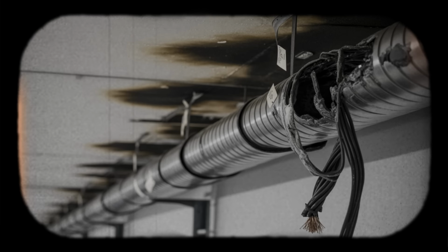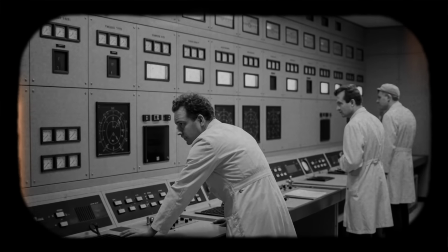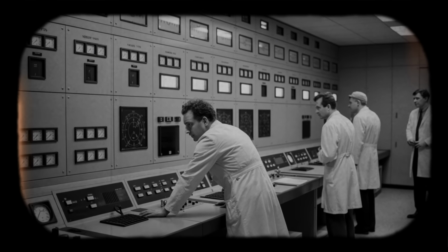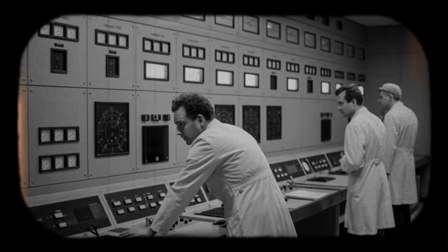The core remained covered and cooled, even as steam generators continued boiling off their remaining water. Heat rejection still occurred through the secondary side, boiling in the steam generators, steam venting to atmosphere, decay heat carried away in that vapor. The boron pump provided the complementary function, maintaining primary inventory against shrinkage and minor leaks, preventing core uncovery. It was fragile. One diesel, one pump. No designed backup if either failed. No procedural guidance for how long this configuration could be sustained, or what would happen if the diesel ran out of fuel or the pump failed mechanically.